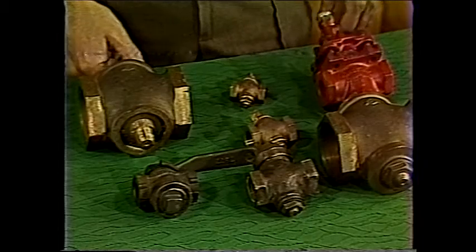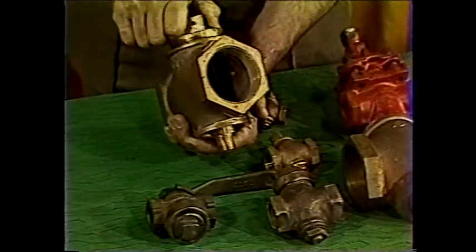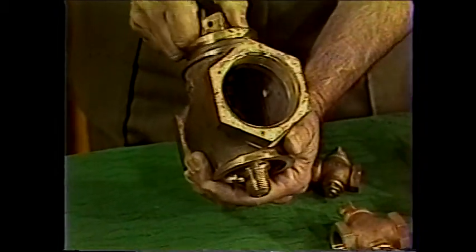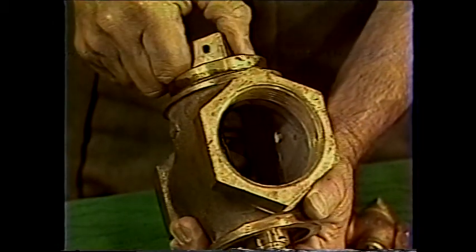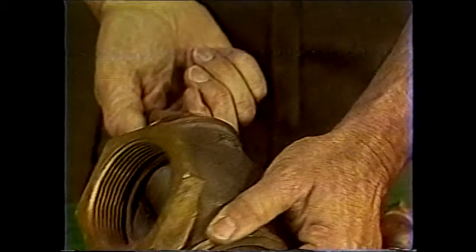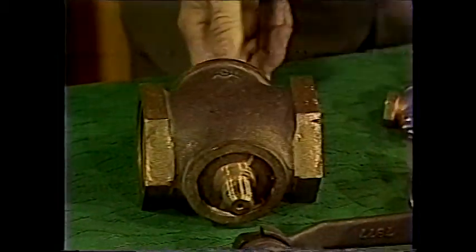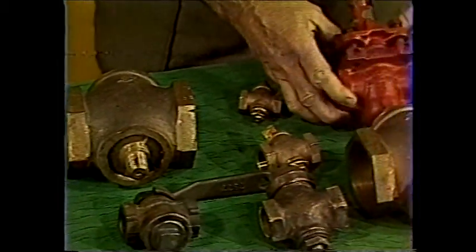Water hammer is actually the term applied to shock, resultant noise, and pressure buildup caused by closing a valve very quickly. It's caused by the energy of a mass of moving fluid which is suddenly stopped. And care should be used when operating plug valves or others such as ball or butterfly, which can be rapidly closed, to make sure that we don't cause damage to the system with water hammer. We will explain ball valves and butterfly valves in a few minutes.